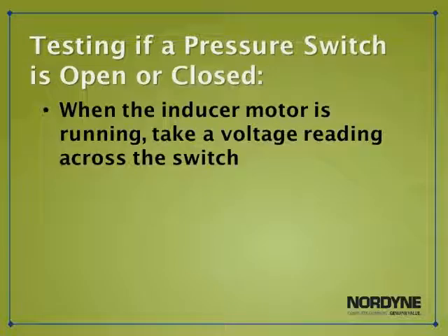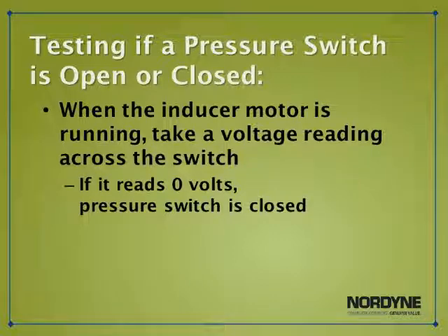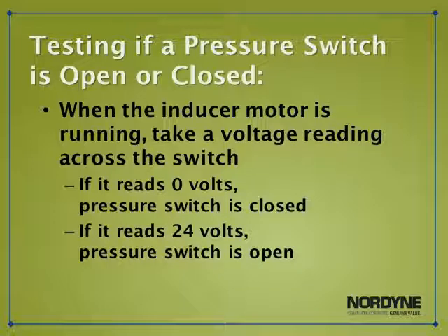One of the easiest ways to test to see if a pressure switch is open or closed is by checking for voltage across the switch. When the inducer motor is running, take a voltage reading across your switch. You should read 0 volts. That would indicate the pressure switch is closed. If the inducer motor is running and you measure 24 volts across the switch, then the switch is open.